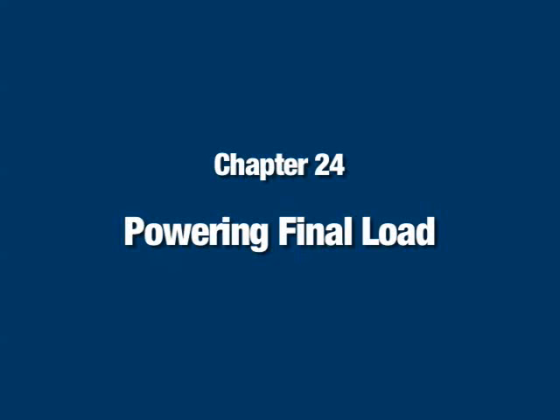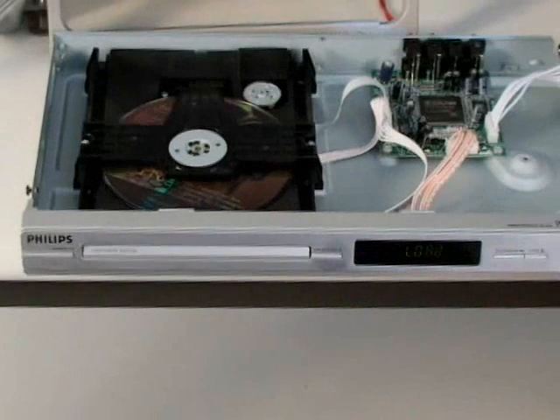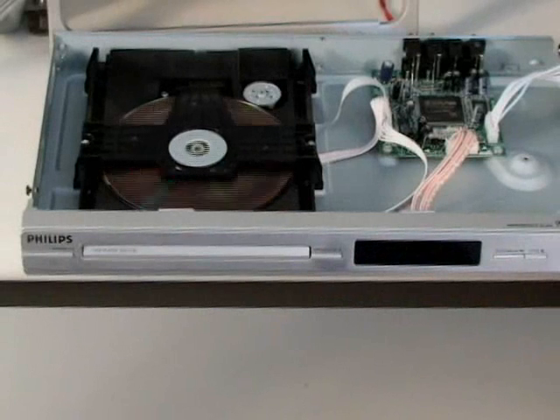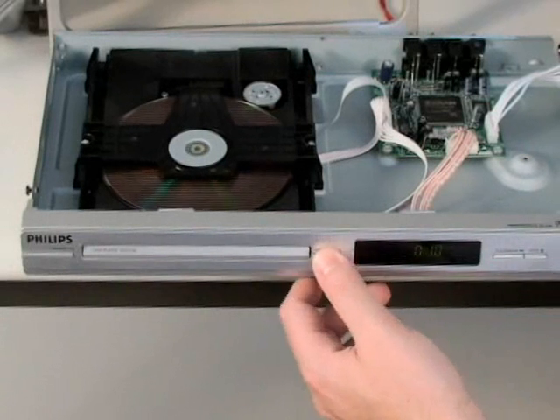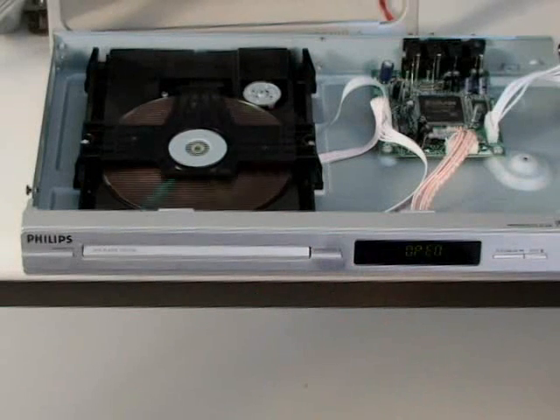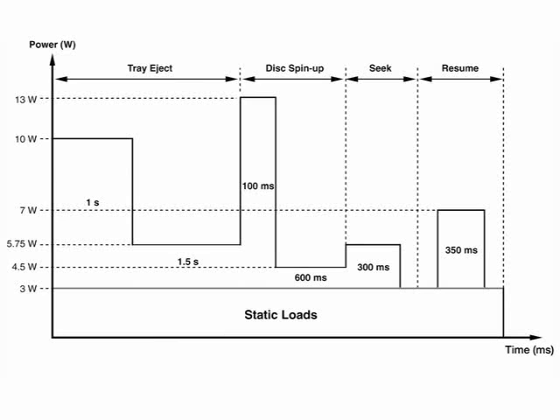Chapter 24, Powering Final Load. If your load has different operational modes, be sure to cycle through all of them and ensure that the power supply never enters auto restart. If it does, your actual load is drawing more power than your supply is designed to deliver. You'll need to carefully characterize your load and redesign your power supply. Refer to the course prerequisites for more information on how to do this.